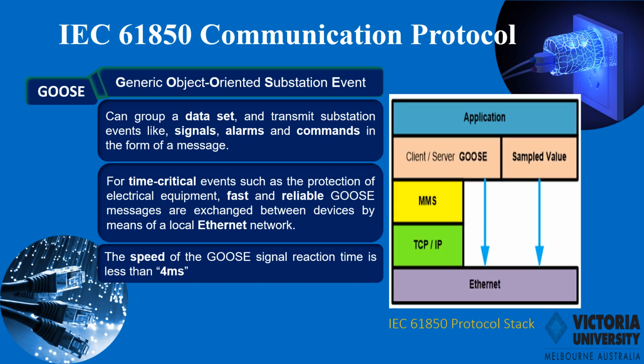That's so quick. For the communication stack mapping shown in the figure, the GOOSE and SV protocols are mapped directly via high-speed messaging on LAN through Ethernet. So the network transmission implies that the data messages carried are of a high level of importance, such as time-critical protection, relaying, interlocking data between IEDs, alarms, signals, and others. Both GOOSE and SV are under layer 2 multicast, which means that they skip other data and communication layers for immediate processing. While MMS is present in most devices for operational reporting and monitoring functions, MMS is not of high importance.